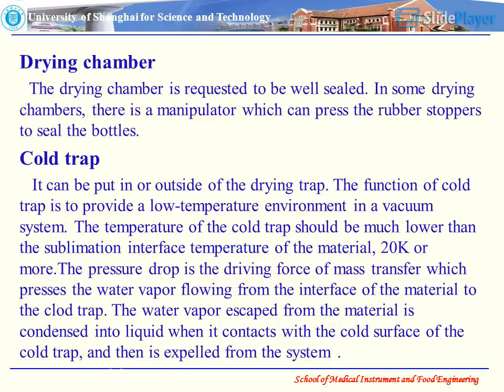Refrigeration system, vacuum system. The task of the refrigeration system is to provide a low temperature environment in the cold trap and/or in the drying chamber. Here, the refrigeration system may be of various types: mechanical vapor compression refrigeration, thermoelectric refrigeration, or using liquid nitrogen directly. The cold trap is the evaporator in the refrigeration system. For the cold trap with low temperature, the two-stage compression refrigeration cycle, or cascade refrigeration cycle, may be adopted.